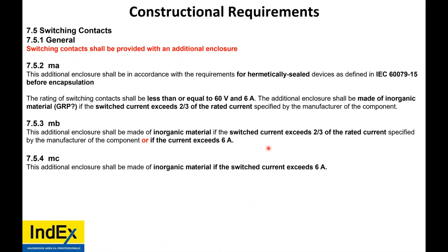So, constructional requirements: switching contacts shall be provided with an additional enclosure. So anything that switches, produces an arc or spark, shall be in a separate enclosure.